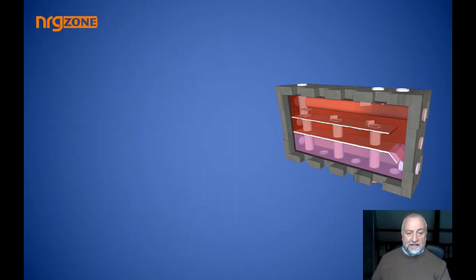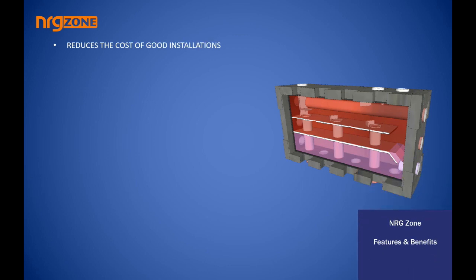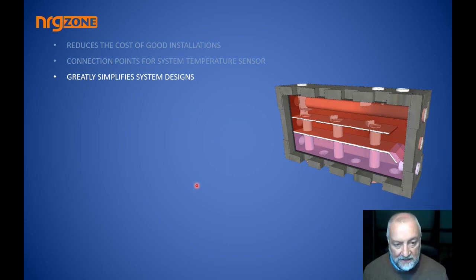So what have we said? We said that the NRG Zone speeds up the process. There's no callbacks. It's easy to understand. It's easy to design. It reduces the cost of installations. There's connection points not just for zones and boilers, but also temperature sensors and the like. It greatly simplifies the design. If I draw a rectangle and I put another rectangle called a boiler to the left, to the right, above, below, whatever, and I connect it to the right thing, I'm off.